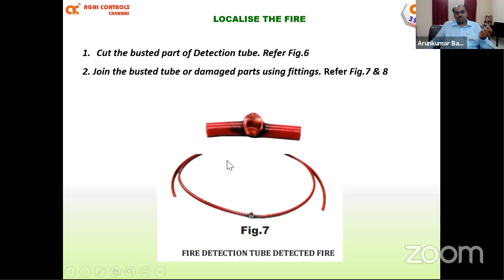What we can do is cut this particular small piece, and then we can use the connectors. There are tube jointing fittings which will also be supplied along with the systems. So that can be used, and a joint like this can be done. Typically you don't need to completely change the entire detection tube. Only the small part where the tube has burst, that part alone we can cut and replace with connecting joints.